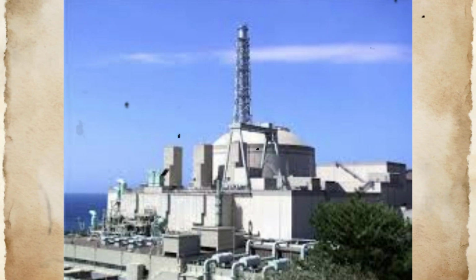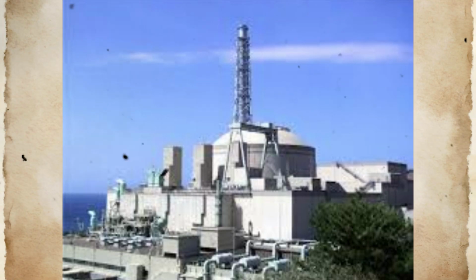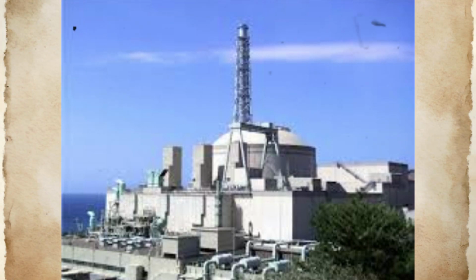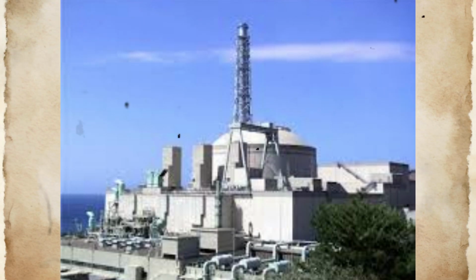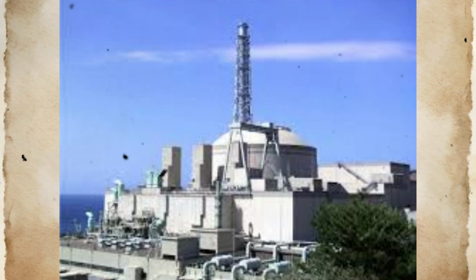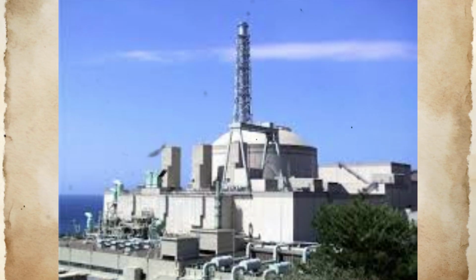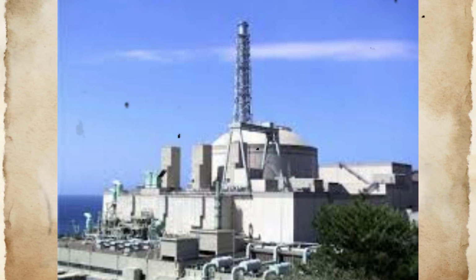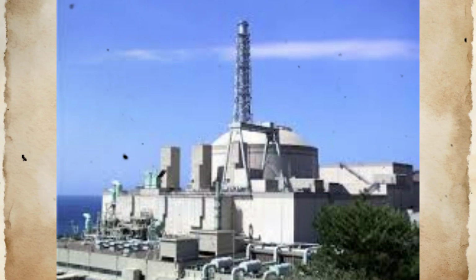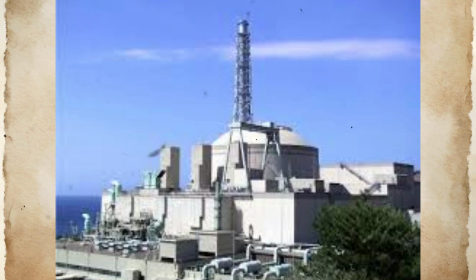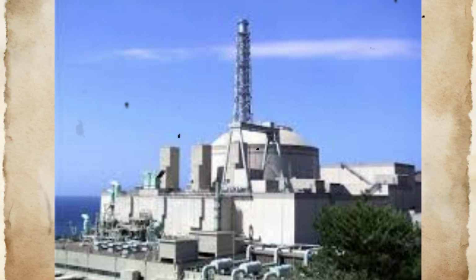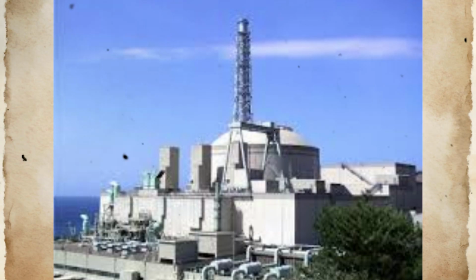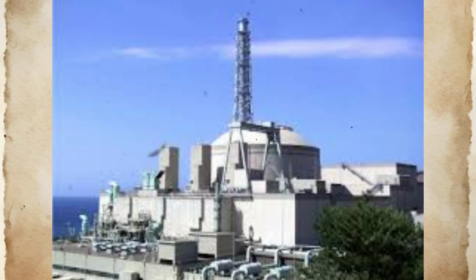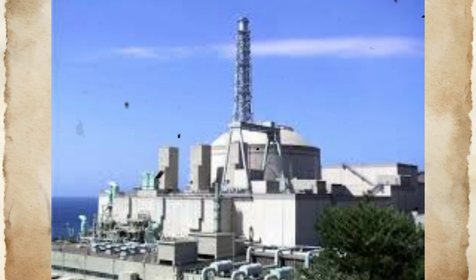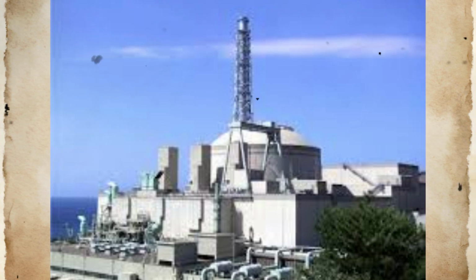The investigation revealed that design guidance available at the time of Monju construction did not adequately address the interaction between thermal performance optimization and mechanical durability under flow-induced vibration conditions. The 1991 Addenda to ASME Boiler and Pressure Vessel Code Section 3 Appendix N, published after Monju design completion, included provisions for vortex-induced vibration prevention that could have prevented this failure.